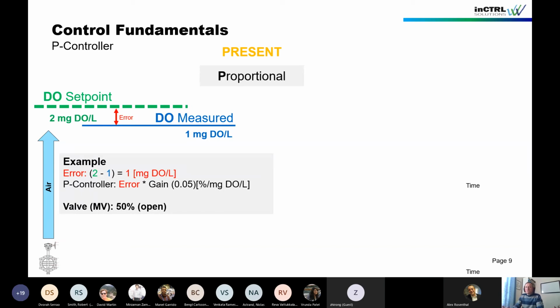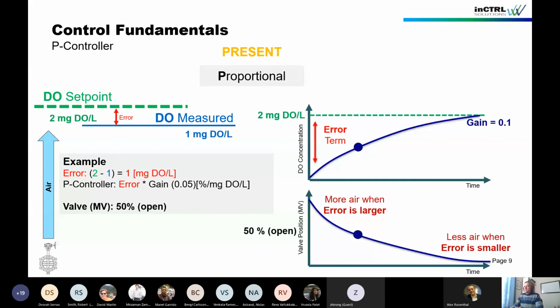In this case, with that gain, the valve position would be 50% open. So basically that means the larger the error, the more air is required. And if the error gets smaller over time, the valve position should get more and more closed as well. That's relatively straightforward.